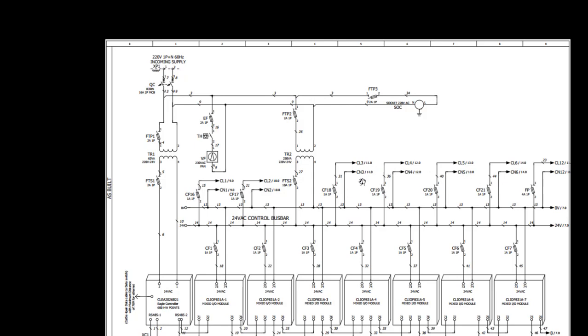So if you want to know where this fuse is feeding, here it is mentioned like 11, this is the page, and 0 means the section of the page. For example, here you can see 0, 1, 2, 3. By clicking this one I can directly go to that page. So if you have the hardware drawing, then you have to go to page number 11 and section 0 of that page, where you will see what this fuse is feeding. Similarly, this fuse is feeding on the 12th page of the drawing. This is on the 13th. You can trace where these fuses are feeding.